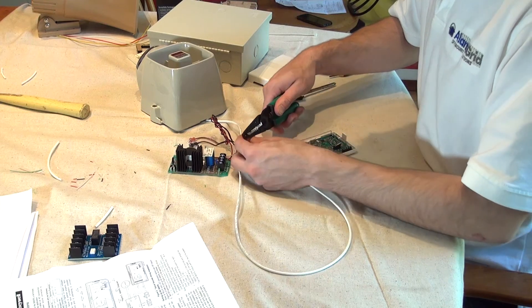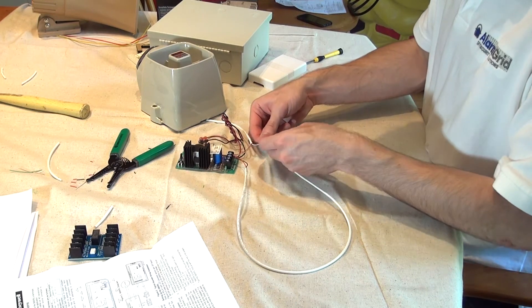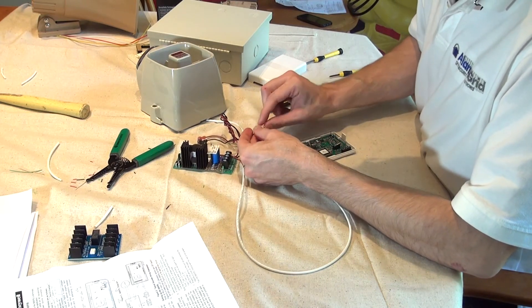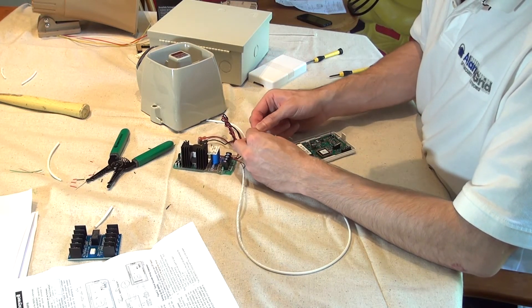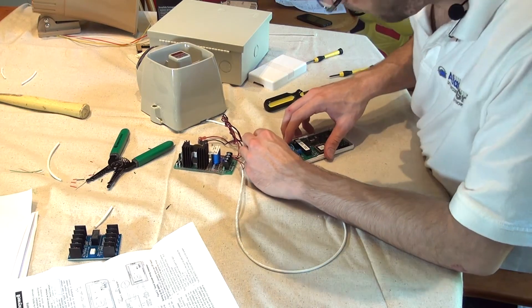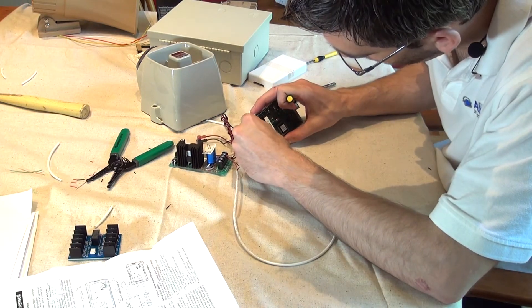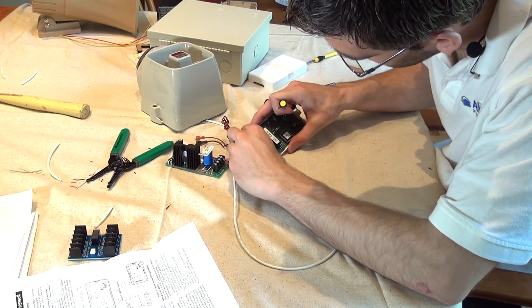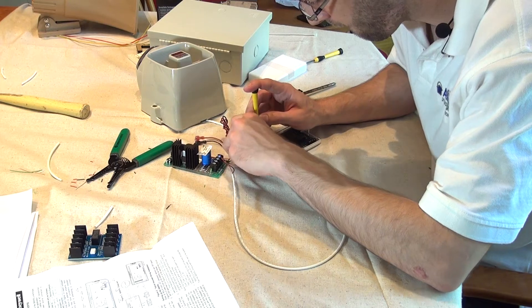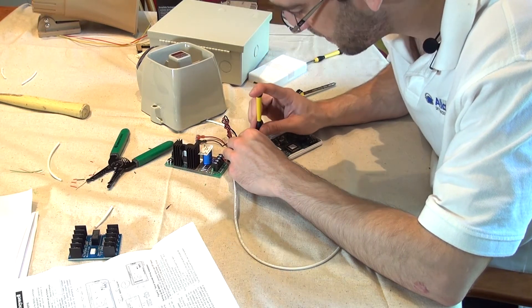We're going to take our two negatives from the siren and the strobe, twist those together, and these are going to get landed to terminal number three on our relay, which is directly underneath the jumper wire connection that we did previously. So we open up the screw terminal, we insert both wires for the siren and the strobe, and we screw it down nice and tight.